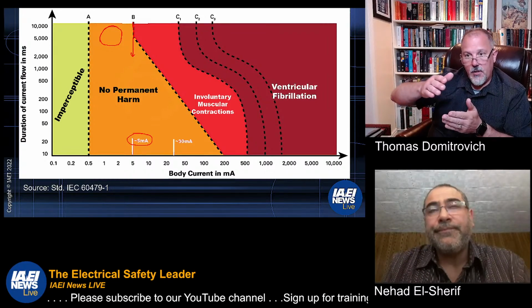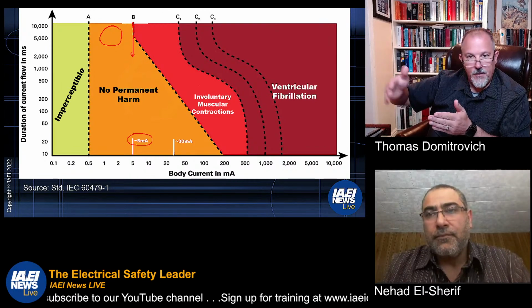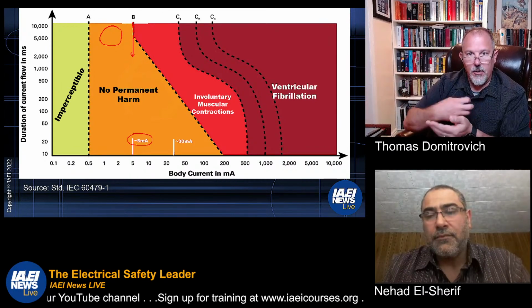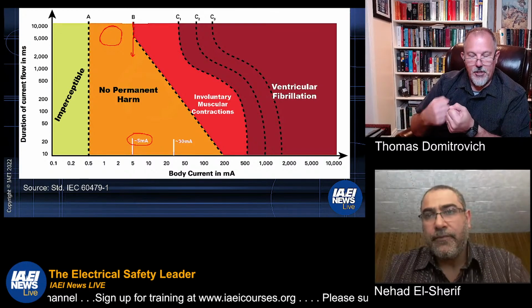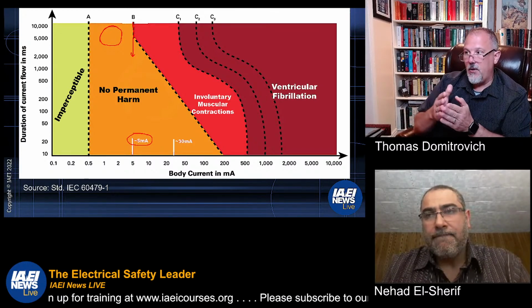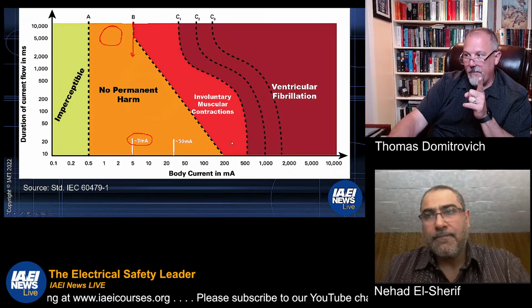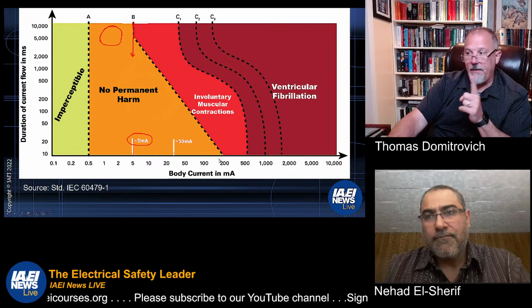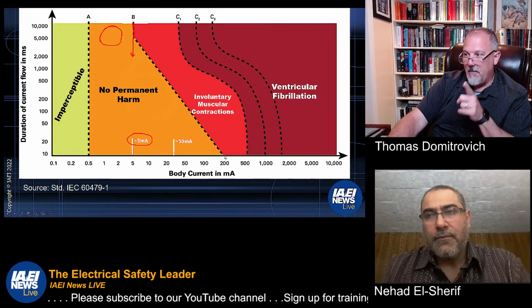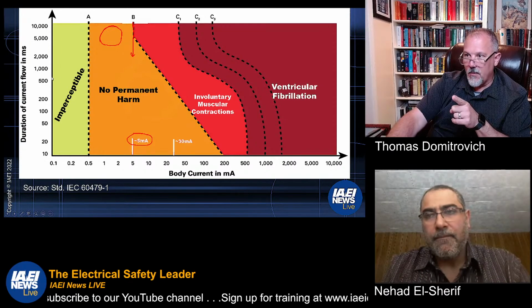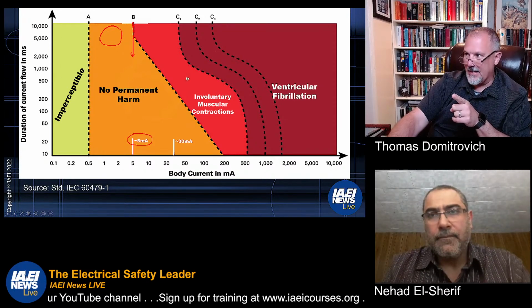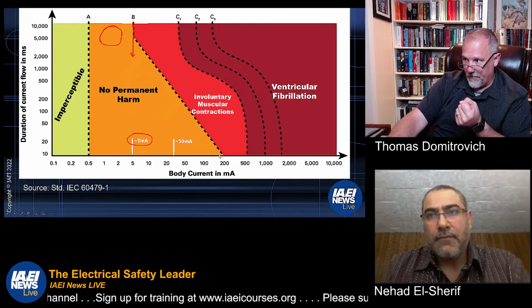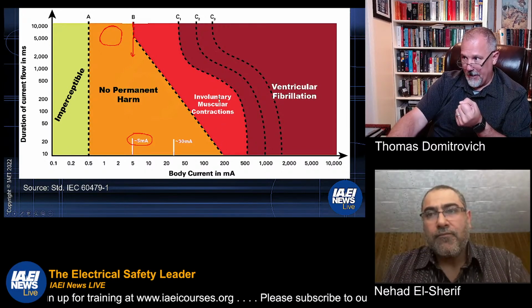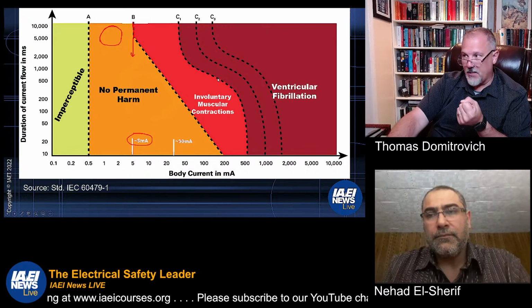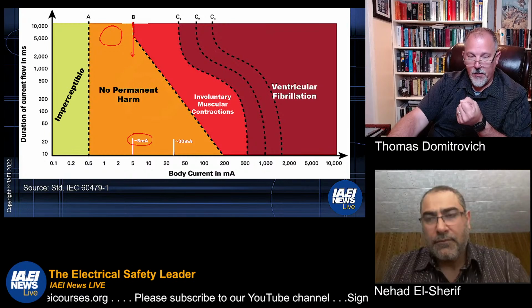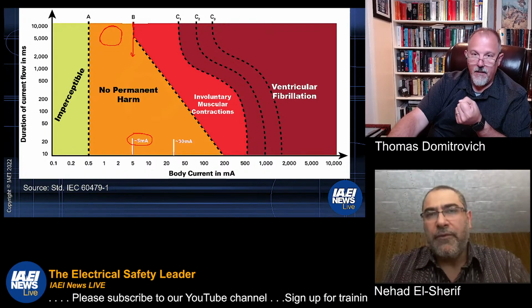Okay, and then to your point, the higher the current you go into, now you're moving into ventricular fibrillation, and now you're getting that heart losing its beat, so to speak, because you're at that 60 hertz frequency, et cetera. And again, it's an equation of current and time. So say 200 milliamps for, say, a little over 500 milliseconds, you're going to have involuntary muscle contractions right off the bat, right? And then the longer that current passes through the body, you'll get to a point where your heart will go into ventricular fibrillation. Exactly.